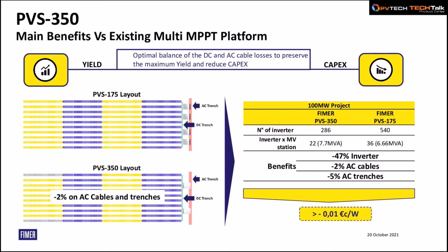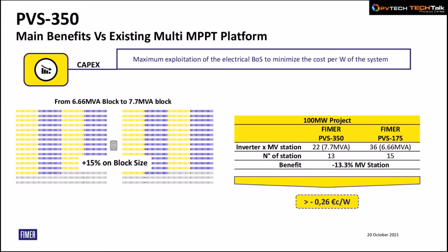The benefits are 47% reduction on inverters, slight reduction on AC cables and trenches, which altogether contribute to 0.01 euro cents per watt at the system level. In terms of Capex, the main benefit is that through a larger capacity inverter, we can promote the adoption of larger MV stations. And this is very important because this plays a significant role in contributing to the capital cost of the system and to the installation cost.